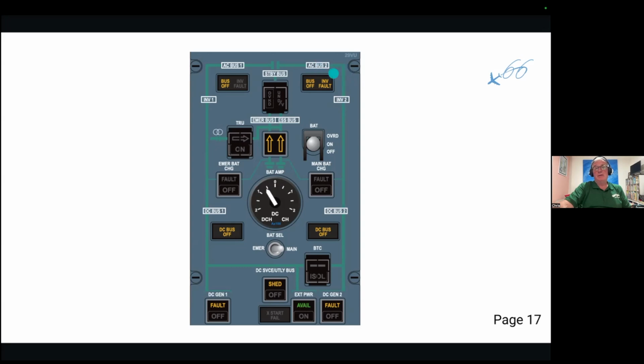And then you'd have DC buses supplied, DC1, DC2, AC buses supplied, AC1, AC2, with at any time a bus tie here, bus tie contactor through a switch, which in its normal operation keeps this isolated.